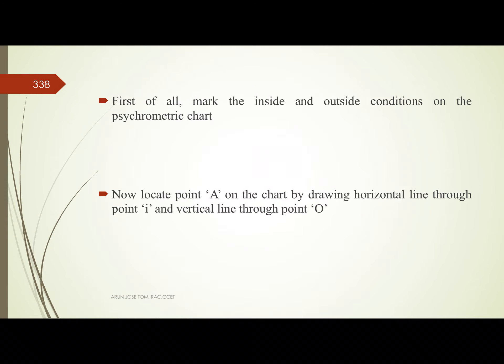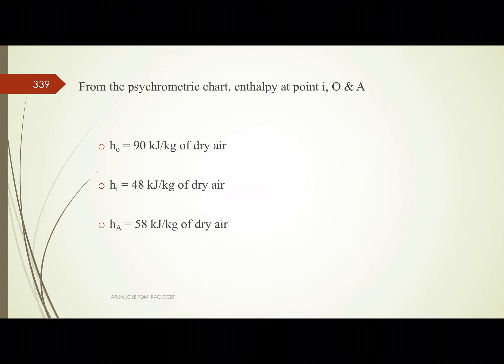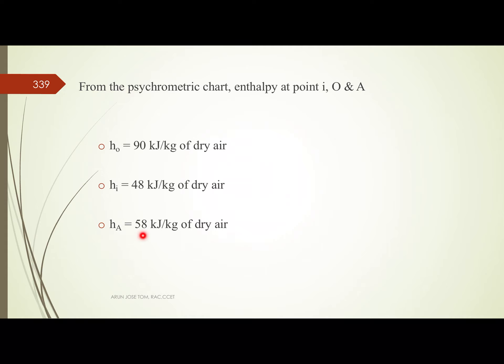We have the inside and outside conditions marked on the psychrometric chart. We mark point A and point O on the chart, and locate the corresponding enthalpies. H_O is 90, H_I is 48, and H_A is 58.